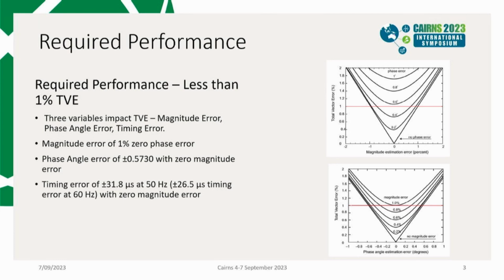So if your magnitude error is 1%, then you are allowed 0 phase error and 0 timing error. Same if you have timing error of 31.8 microseconds at 50 hertz in either direction, then you are allowed 0 magnitude error. So the implementation that was required to meet this was very arduous. And a lot of the research in the initial component of the project was to do this.